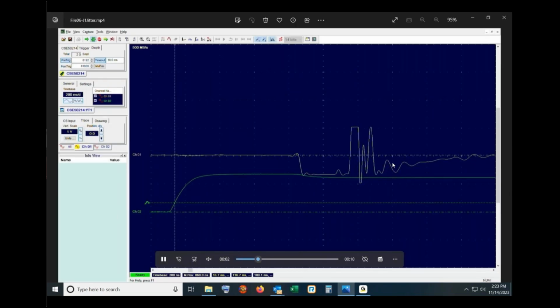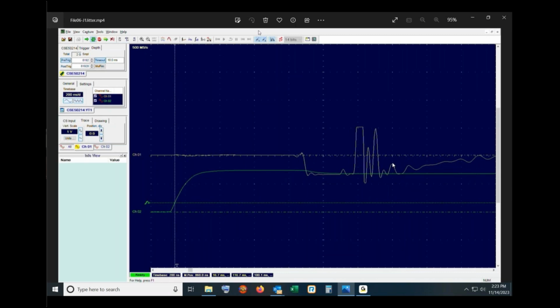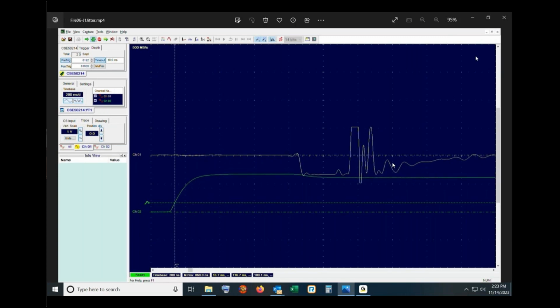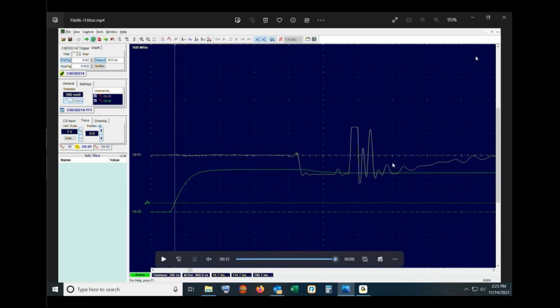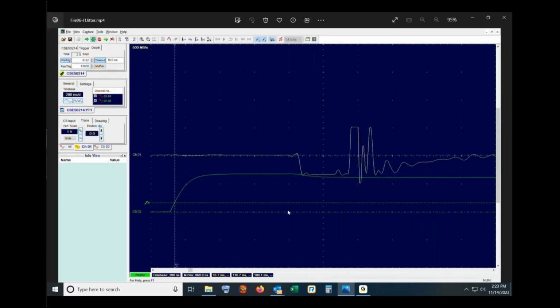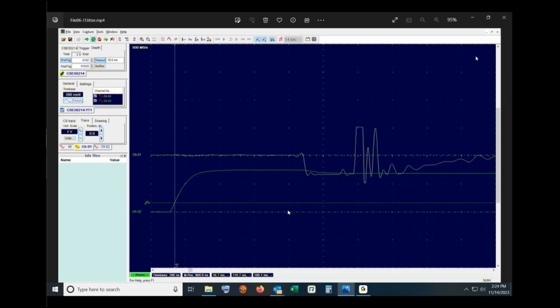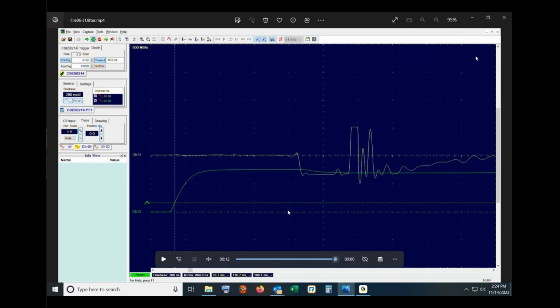Here what I've done is we're looking at the ultrasonic signal itself in yellow on channel 1, and the trigger signal, the trigger pulse, on channel 2. Normally I would connect that to the external trigger input, but since we weren't using channel 2 anyway, I figured it was good for illustration purposes. You can see we're triggering on that external trigger pulse, and the ultrasonic echo always comes quite quickly afterwards. What we notice right away is that things are jittering around and the amplitude of the external trigger pulse is jumping up and down. That's no failing of the digitizer card. That's actually a broken pulser receiver.